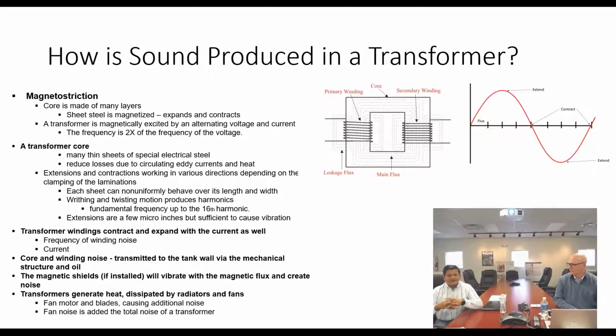If the extension and contraction, as described above, are taking place in various directions, depending upon the clamping of the lamination, each sheet can behave non-uniformly over the length and width. This writhing and twisting motion produces harmonics of the fundamental frequency up to the 16th harmonic, so 16 times the cycle of the current. These extensions are a few micro inches dimensionally. However, they are sufficient to cause vibration as noise, and this is the core noise.